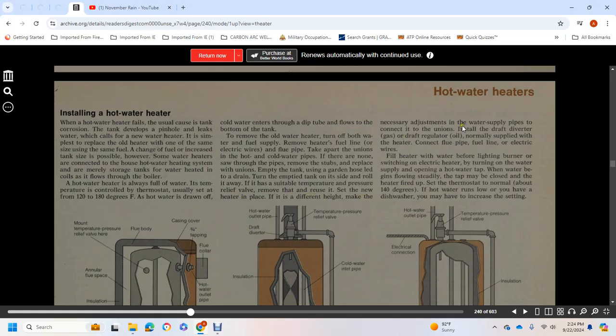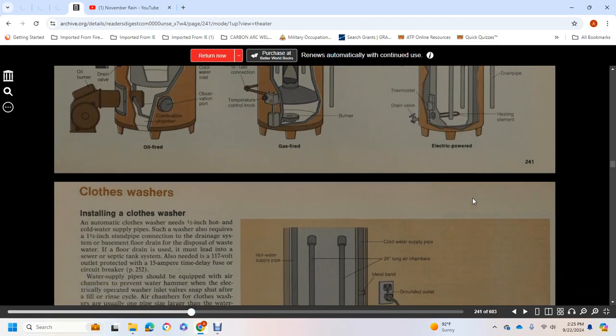Make sure necessary adjustments to the water supply pipes have been made to connect to your unit. Install the draft diverter for gas, or the draft regulator for oil, normally supplied with the heater. Connect the flue lines, fuel line, and electrical wires. Fill the heater with water before lighting the burner or switching on the electrical heater, with the supply open and a hot water tap open. When water begins flowing steadily, the tap may be closed and the heater fired up. Since the thermostat is normally set at about 140 degrees, if the hot water runs low or you have a dishwasher, you may have to increase the setting.